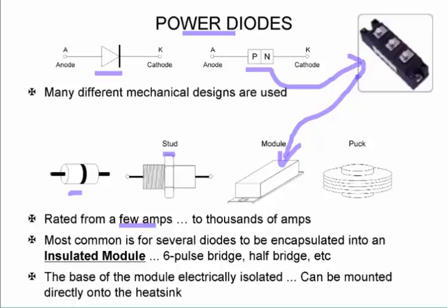is your insulated module which has got a 6 pulse bridge. So there are 6 diodes basically in this module. Now the base of this module is electrically isolated and that means we can directly mount it on the heat sink.